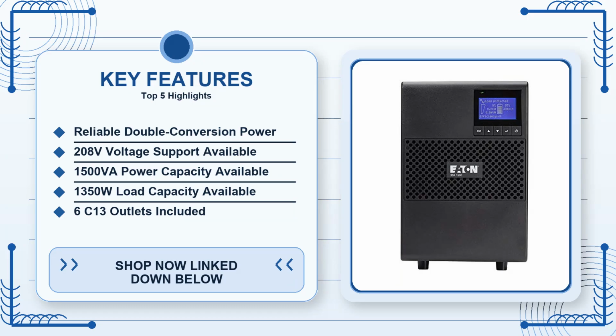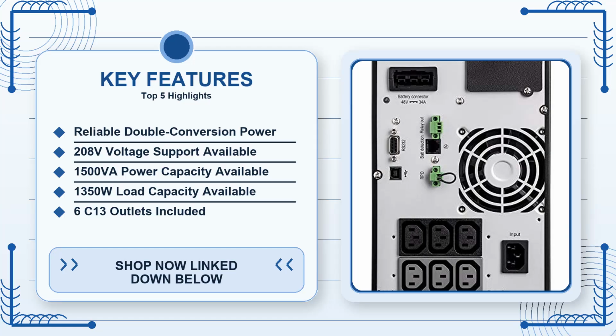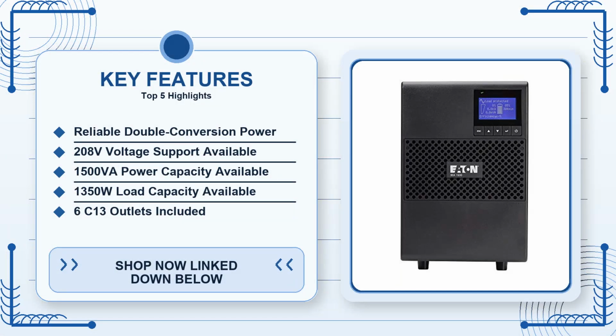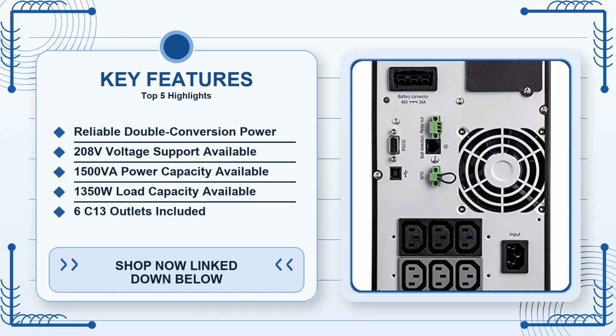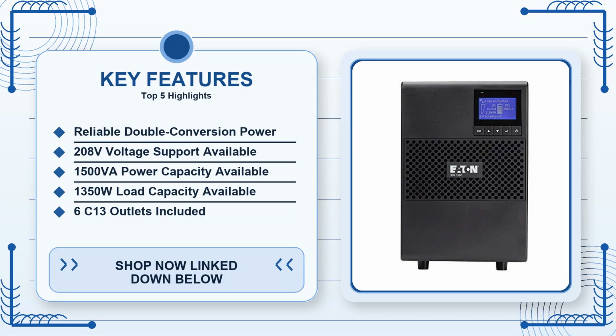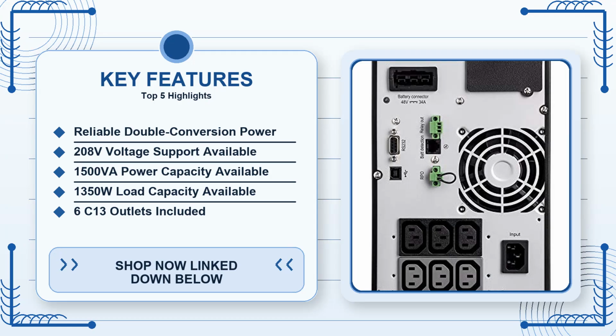Likewise, if you need a UPS that can sustain a long outage, say, you live in an area prone to grid failures lasting 30 minutes or more, you'll want a unit with a larger battery bank or the ability to chain additional external batteries. On the downside, the unit's silent mode fan is a trade-off you may notice in a quiet office. When the temperature rises, the fan steps up to maintain cooling, and the noise can become audible.